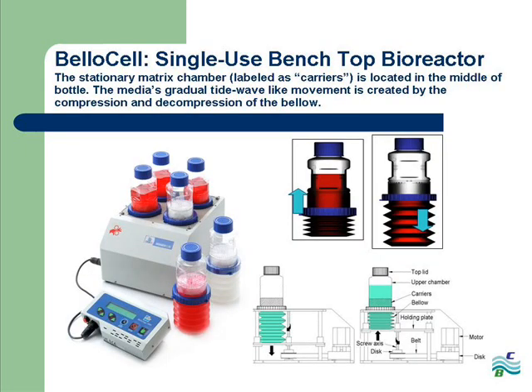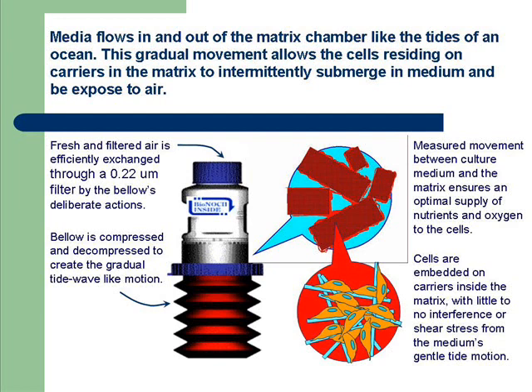In our bench top lab system, BelloCell, the stationary matrix chamber is located in the middle of the BelloCell bottle containing a high density of cells attached to carriers. The compression and decompression of the bellow beneath this matrix chamber adapts the roller bottle TIDE principle with its gradual tide wave-like motion. This gradual motion allows for optimal oxygen and nutrient transfer into the cells residing on the carriers inside the stationary matrix. The measured movements of the bellow draw air through the top filter and alternately submerge the cells in nutrient-rich media. The cells embedded on the carriers in the matrix are undisturbed, experiencing little to no shear stress.